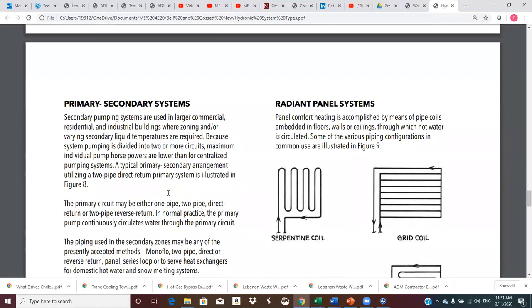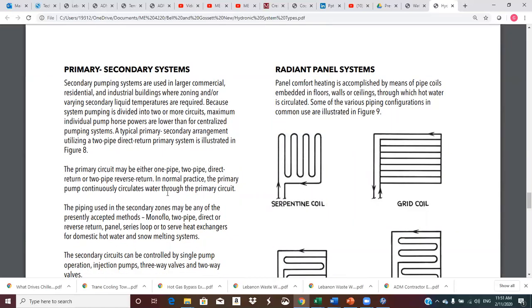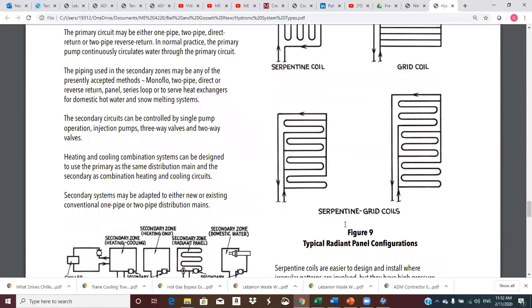And then this is radiant panel systems. There are different ways to pipe them up. With this one, if you have hot water coming in here, the water cools down continuously as it goes through, so this one over here is going to get much colder water than this one over here, and that may cause a problem. So you can supply to a header situation where we have our hot water coming in here and we pull off a little bit. Each one of these crossing pipes gets the same temperature of water, because this is our main water. It comes up, goes through this way, and then returns. You've got serpentine and grid coils. You've got all kinds of options for this.